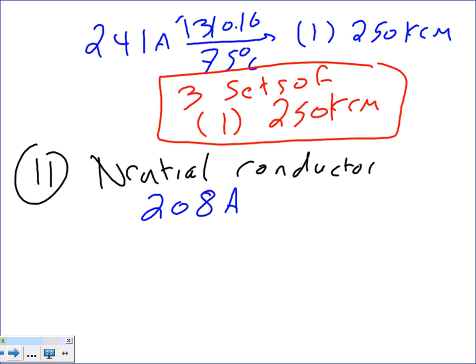Okay. Now we're paralleling conductors, and we have a neutral. So how are you going to do that? If you parallel the conductors, guys, we have to put the neutral and the three phases all in one conduit. The neutral and the three phases all in one conduit.